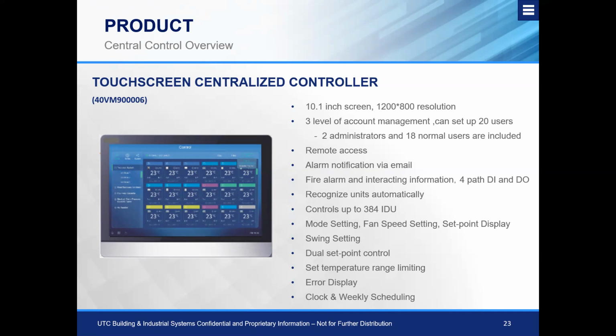You can set up alarm notification via email, fire alarm, and interacting information with 4 digital input and digital output. Next part of this is you don't have to essentially write a program and send it to the centralized controller. When we have everything hooked up, all we do is tie 2 wires from the centralized controller into the outdoor unit, and then hit the auto search when we're configuring this, and this automatically recognizes all of the systems that are hooked up to the centralized controller, which really makes it seamless for control integration. We can control 384 indoor units in total between multiple systems.